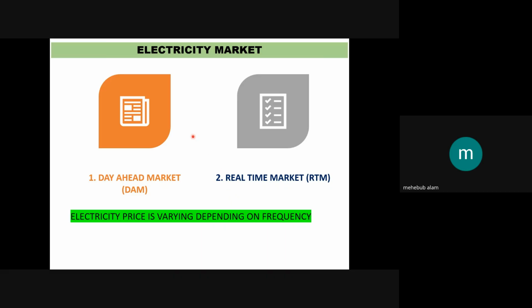And in that context, basically two types of market are there. One is the day-ahead market, known as DAM, and the second is the RTM, the real-time market. And an interesting fact is that the electricity price varies depending on the frequency. As a domestic consumer, we take power from the DISCOM at a fixed price, like 6 or 7 rupees. But from the generator's viewpoint, when the generator is pushing power into the grid and selling power to the consumer, the generator will not get the tariff at a fixed rate. There will be two parts, a fixed cost and a variable cost. The variable cost will depend on the frequency and will be guided by DSM.